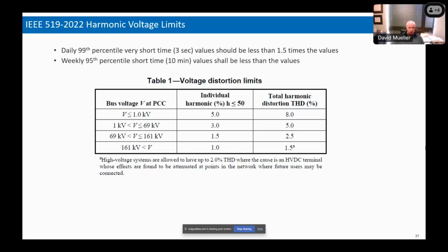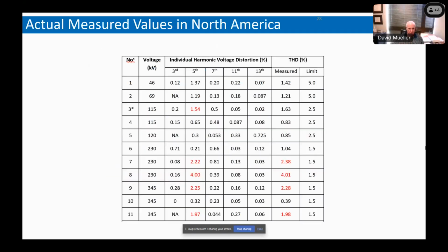So in Europe, when they apply harmonic voltage limits and they have a limit of 3 or 4%, there is some headroom. There is some room for the IBR to cause some increase without being a problem. But with our IEEE 519 limits in the US, in many cases, we're already over the limit. There is no headroom. We're already in the hole in terms of what we're going to do.